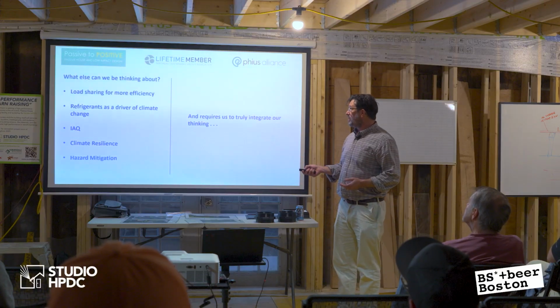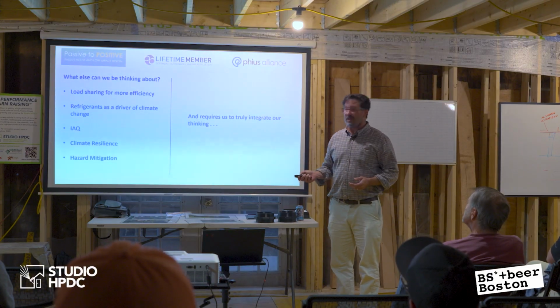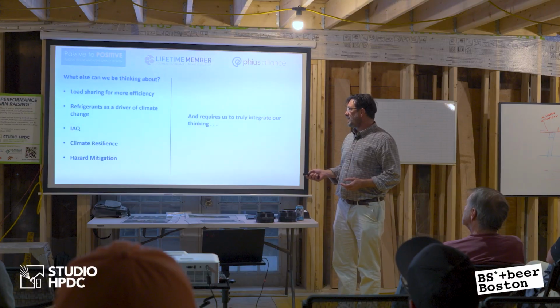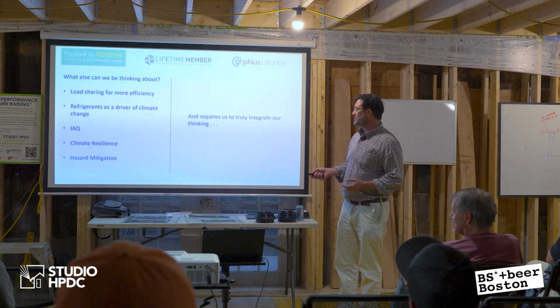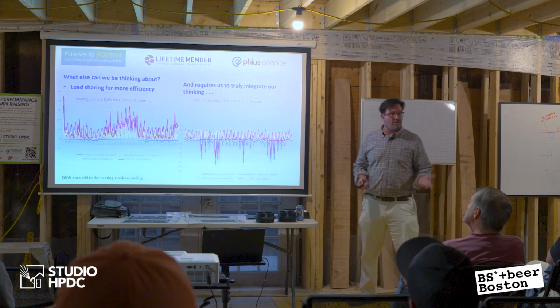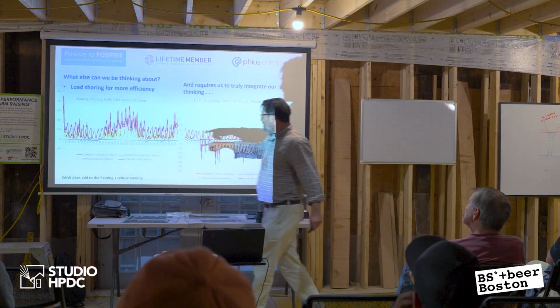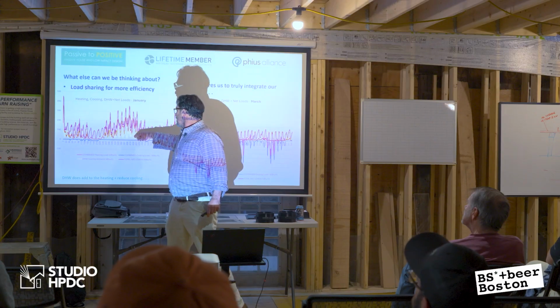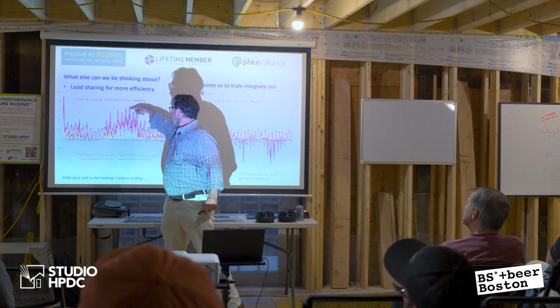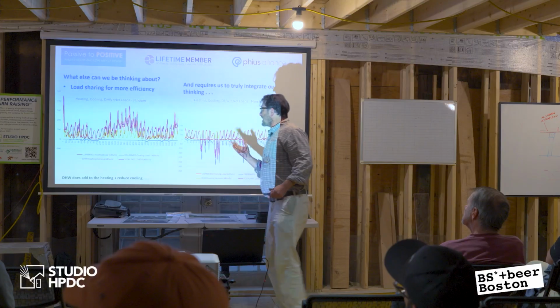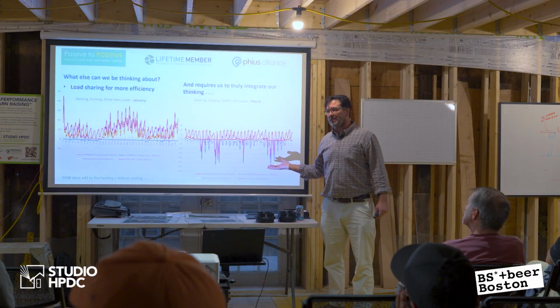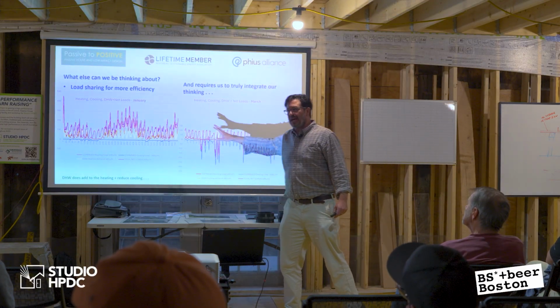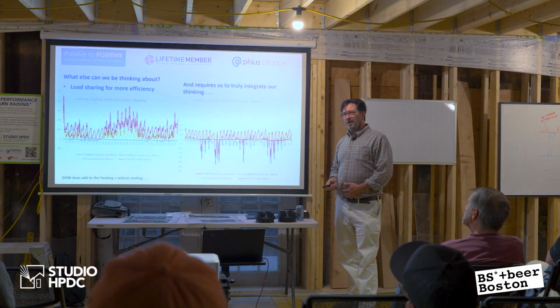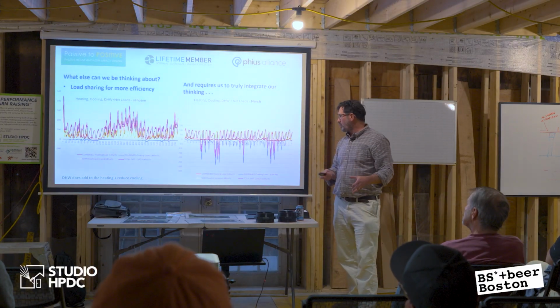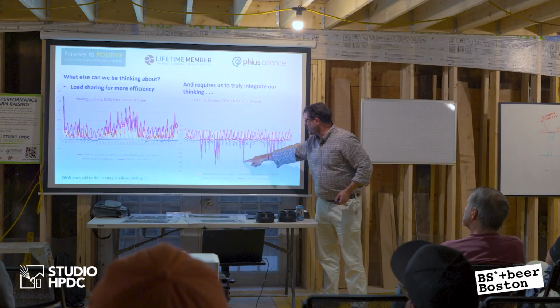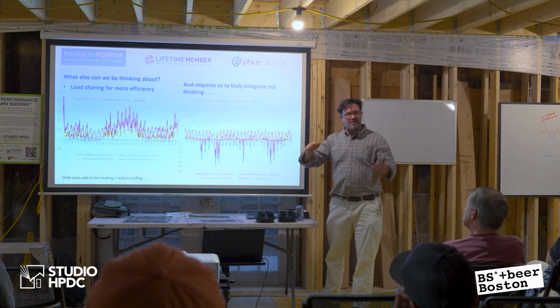You might be able to talk about how refrigerants are a driver of climate change, or your indoor air quality concerns, climate resilience, hazard mitigation. Those are all very closely related. So on this project, we're actually trying to think about these things. This is another project, but here's my domestic hot water load. Here's my heating load, but I can add 30% to my heating load. In this case, that was really important because it was a cooling load dominated building. So I'll do a little extra in the wintertime and I can reduce my cooling load by taking the heat from the air and putting it into the water. So this is where our cooling loads get reduced. So then we're able to balance the system.